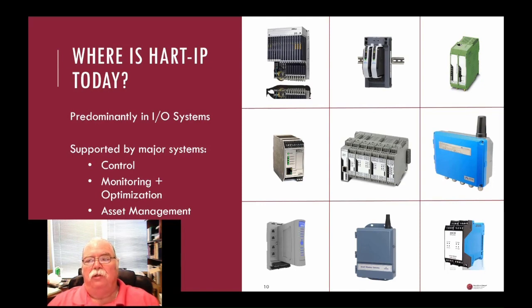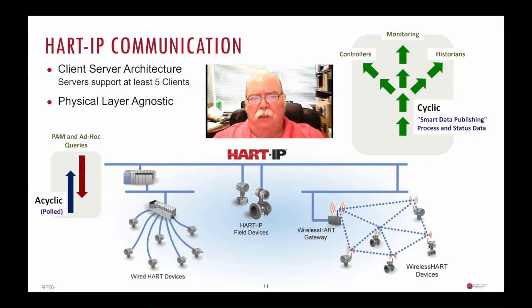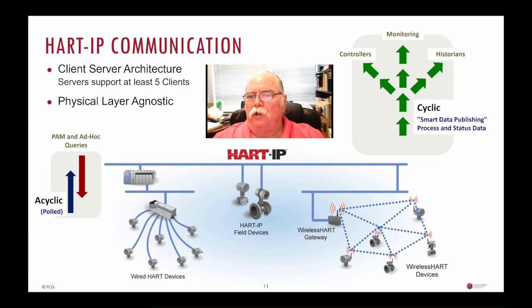Today, all major hosts support HART IP. HART IP is a client-server-based architecture — all field devices and remote I/O are servers, providing data about plant operation up to clients. HART IP requires that servers, whether field devices or I/O, support at least five clients. This allows for redundant controllers, plus plant asset management, plus some monitoring and optimization before you run out of client connections.